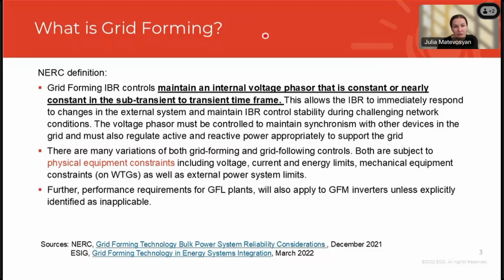There are many variations of both grid forming and grid following controls. Both are subject to physical equipment limits. And when we talk about grid forming specifications, we need to keep in mind that for the most part, grid following IBR requirements also apply unless there is a conflict, and then it's discussed separately.